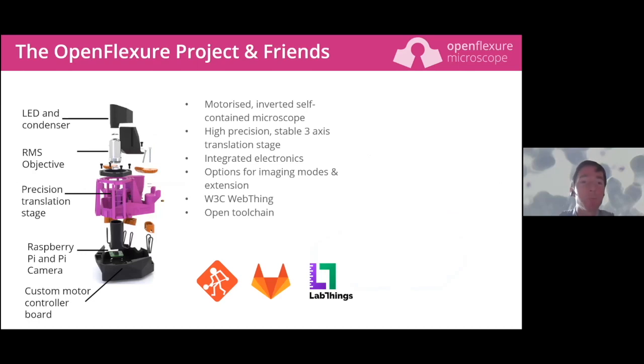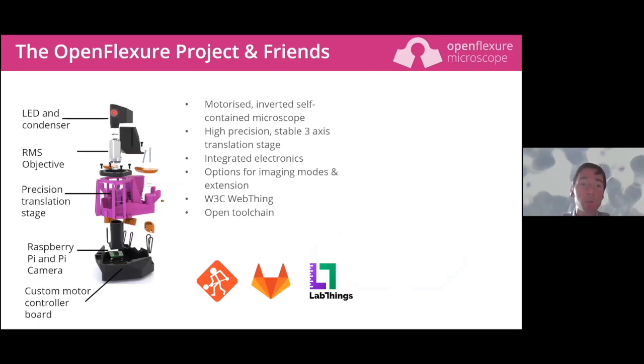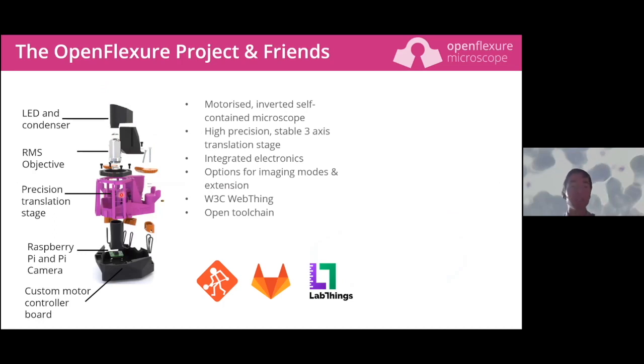So what does the OpenFlexure microscope look like? It's got most parts you'd expect in a typical lab microscope. There's a condenser at the top with an LED illumination source, a condenser lens, a microscope objective, a tube lens in the middle, and a precision translation stage for X, Y, and Z movement. At the bottom there's a Raspberry Pi, a camera, and a motor board so everything can be automated. It's a fully motorized inverted microscope, self-contained with all electronics inside the box.